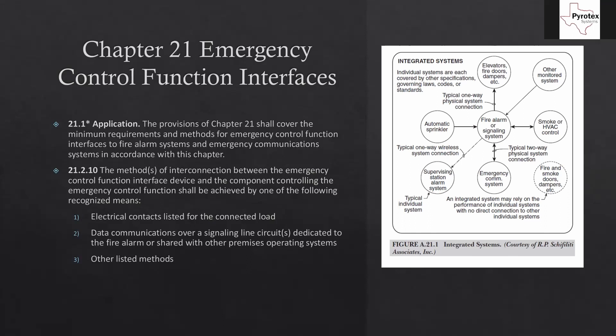Up at the top we have the elevator, fire doors, and dampers. There's no signal for them to send back to us — we're just telling them what to do. Other monitored systems could be like a kitchen hood or something else in the building that we just need to know the status of, so that's just an input to us. Same with sprinkler systems — they're just an input. The last one is the supervising station alarm, the central station we send everything out to over phone lines, cellular, or IP. That's a one-way communication; the central station doesn't send us a signal back — they just receive the alarm signals and report to the customer.